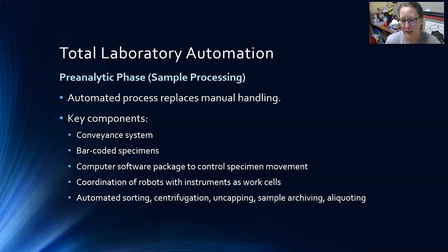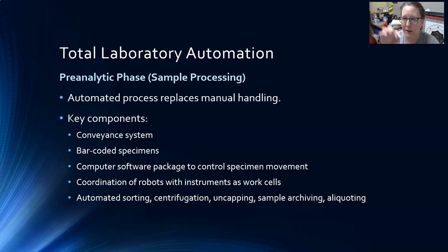Sample archiving is also handled — once all testing is completed, the sample is returned to a storage area. If you need to retrieve the sample hours later to add tests or verify something, you can search for it in the storage end of the system. The machine knows where it put the sample, so it can find it, retrieve it, maybe add a test, and send it back through the system.